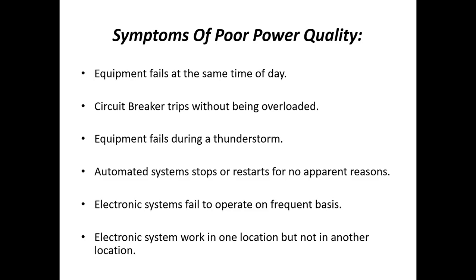The second thing: if a voltage swell is there, or more current is there, a circuit breaker trips without being overloaded. That may happen. Then equipment fails during a thunderstorm. When a thunderstorm is there, there may be chances of high voltage, that means lightning strokes. If a lightning stroke occurs, the voltage of that equipment may increase because of it, and the particular equipment may be damaged or fail.